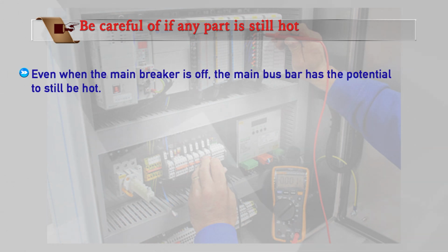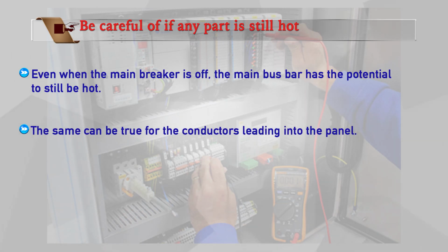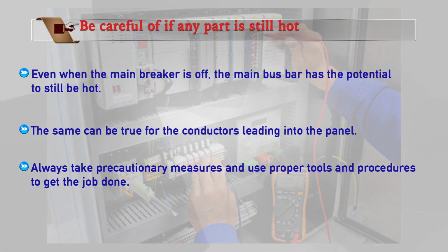Even when the main breaker is off, the main bus bar has the potential to still be hot. The same can be true for the conductor leading into the panel. Always take precautionary measures and use proper tools and procedure to get the job done. Next point is inspect before turning on the circuit breaker.